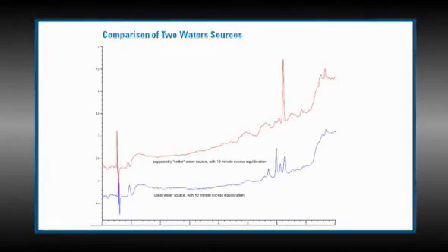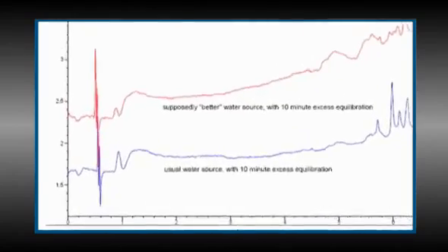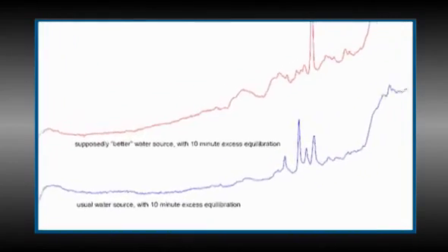Note that the purification performance of in-house water systems is monitored based on conductivity and not on UV absorbance. Conductivity is a measure of ionic purity, but not of UV purity. In your in-house purification system, it may be necessary to change the activated charcoal filters more often. Some users prefer purifying water by using an old reverse phase prep column, and this will remove hydrophobic contaminants from water that has passed through it. You can change water sources and see if the ghost peaks are eliminated or changed. This chromatogram shows a difference in baseline from different sources of water.